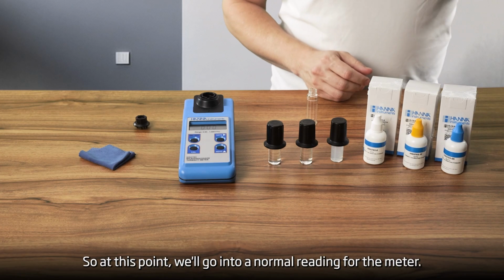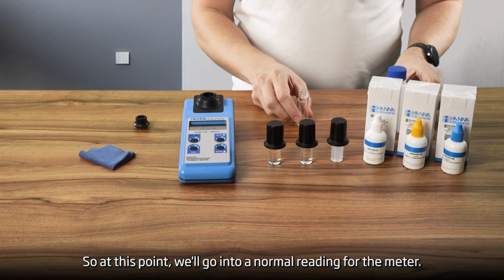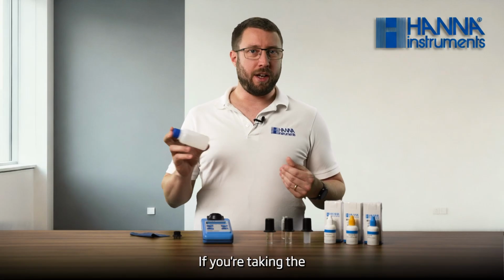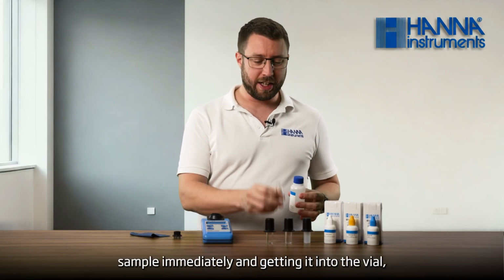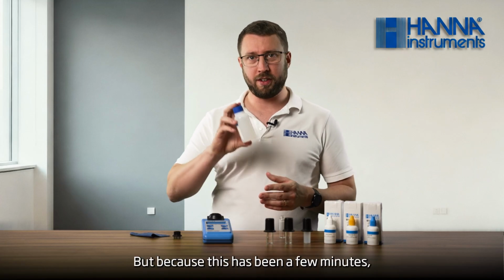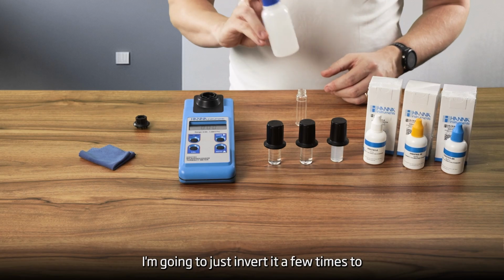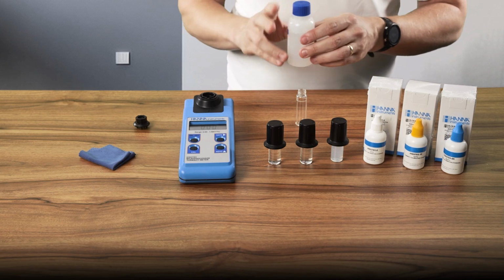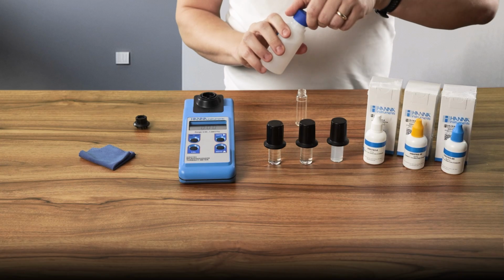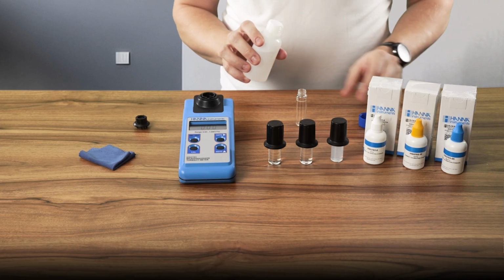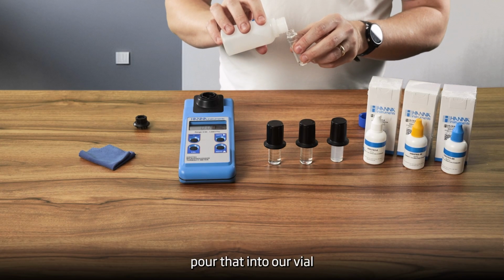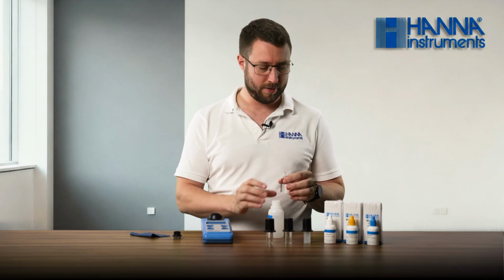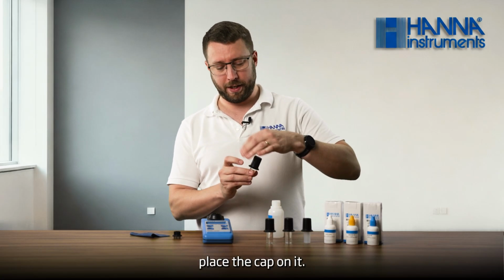So at this point we'll go into a normal reading for the meter. So we've got our sample here. If you're taking the sample immediately and getting it into the vial, that's great. But because this has been a few minutes, I'm going to just invert it a few times to homogenize it. Pour that into our vial, up to the line. Place the cap on it.